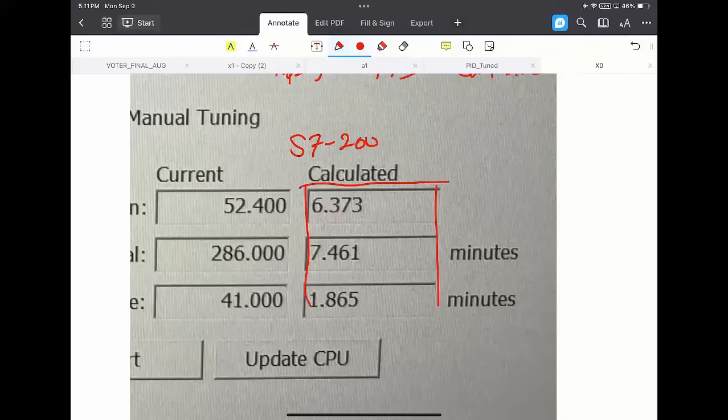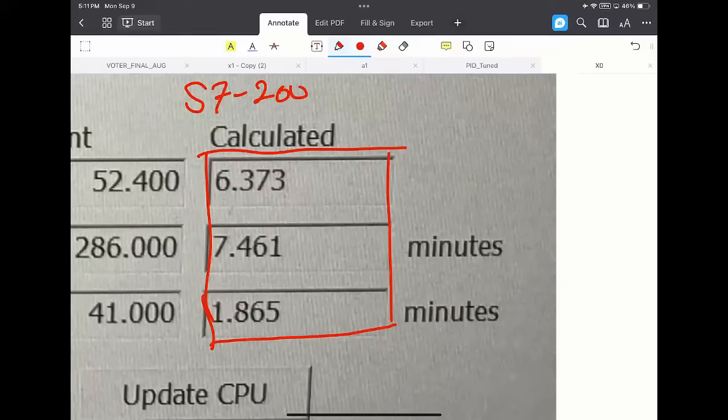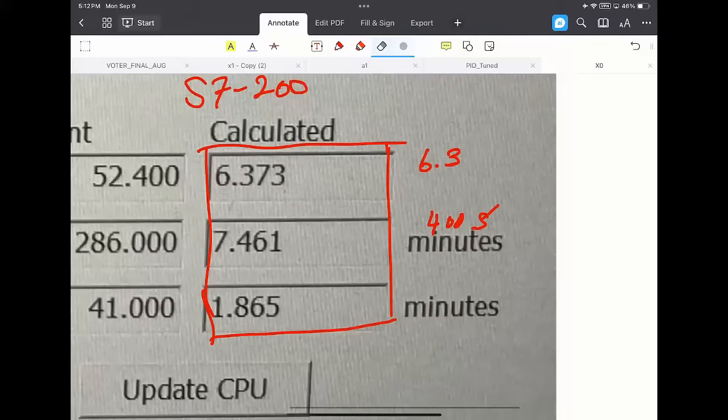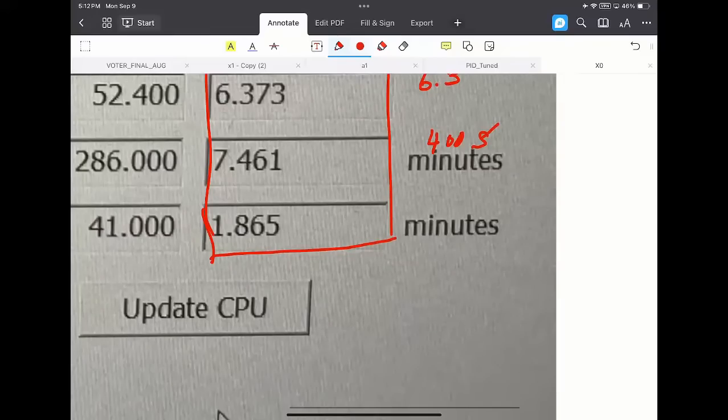These values, for me, based on my information and memory, these are aggressive values. If we put them on a heating process, we may encounter too much excessive heating and it may cause the waste of energy. The gain of 6.3 and the integration time of around 400 seconds and the derivative part, the TD of 120 seconds.